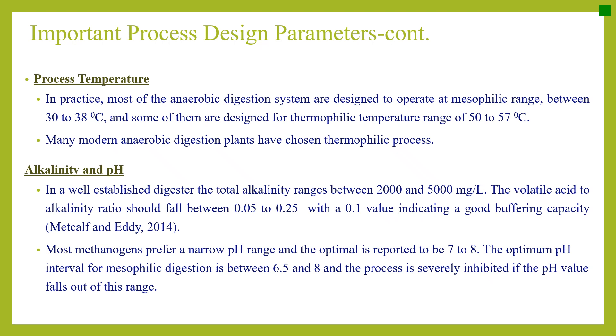The next parameter is alkalinity and pH. For a well-established digester, the total alkalinity range should be between 2000 and 5000 mg per litre. The volatile acid to alkalinity ratio should fall between 0.05 to 0.25, with a value of 0.1 indicating good buffering capacity. The optimal pH range for methanogens is reported to be 7 to 8, and the optimum pH interval for mesophilic digestion is between 6.5 and 8. The process is severely inhibited if pH falls outside this range.